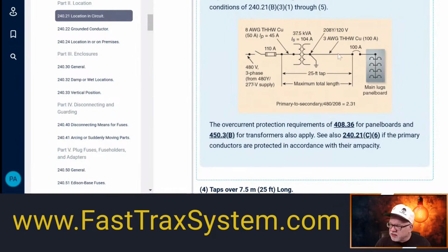So they size this conductor, and they need it to be what? So this right here, maximum output is 104. They're doing a 100 amp panel. Perfectly fine. That's what they've calculated their load to be. And this conductor right here has to be equal to or greater than the device it connects into. Right? That's under the normal rules, right? But now we're doing this 25-foot tap rule. So let's see if everything works out based on our rules.